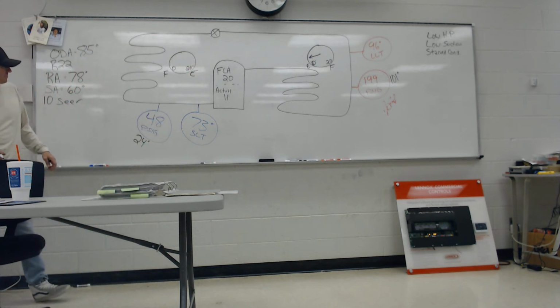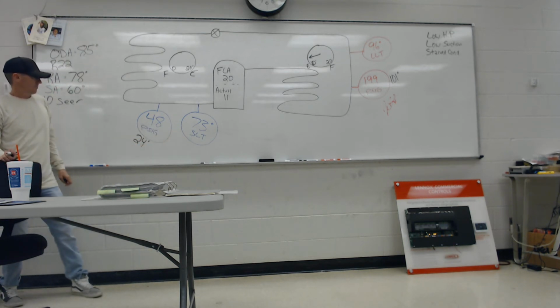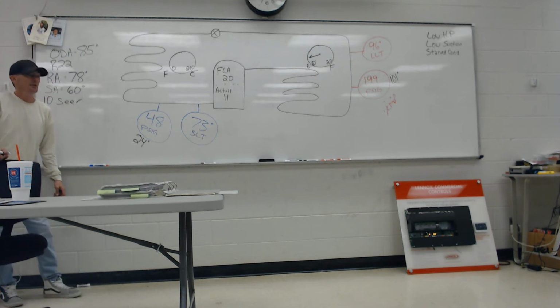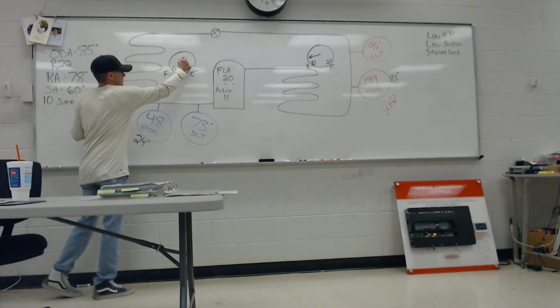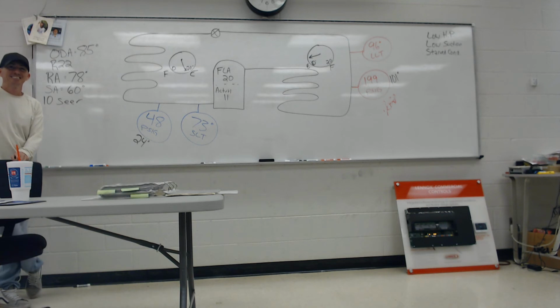I've got 49 degrees. That is definitely empty. Better find a gas station, right? Empty, starved, leak. High superheat means high vapor, which means low liquid.